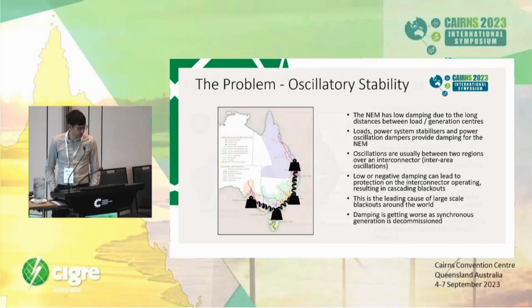So as I said, because of the long nature, we've got this oscillatory stability problem, oscillations between different groups of generators in the states. The oscillations are usually on the order of 0.5 to around 2 or 3 hertz. And we have lots of loads, power system stabilizers on generators, and oscillation dampers on SVCs to help us manage the problem. But as the synchronous generators become decommitted, as they retire, we lose that oscillation damping on the system, and it's a service that isn't currently provided by inverter-based resources or batteries at the moment.